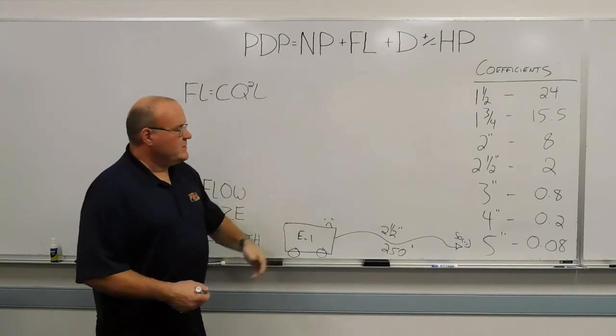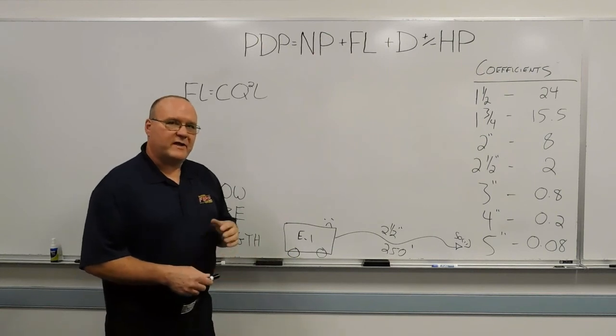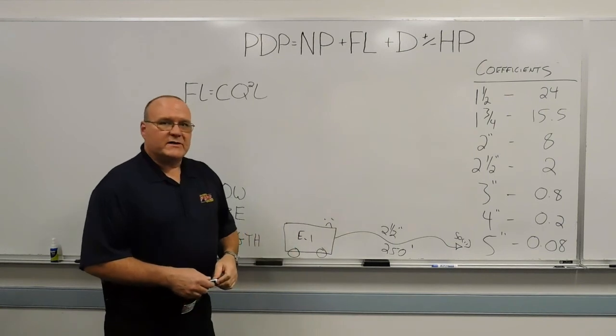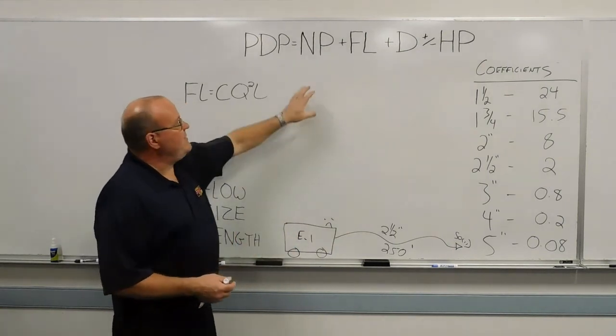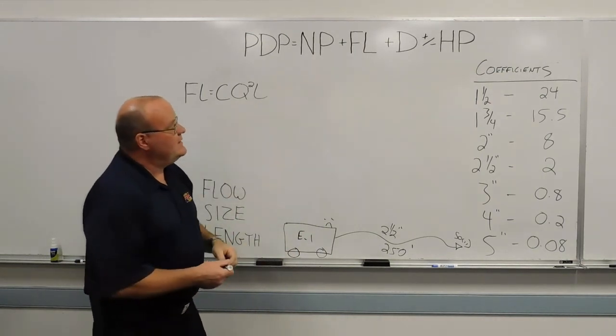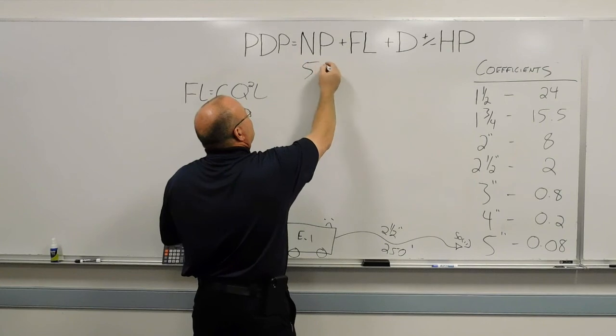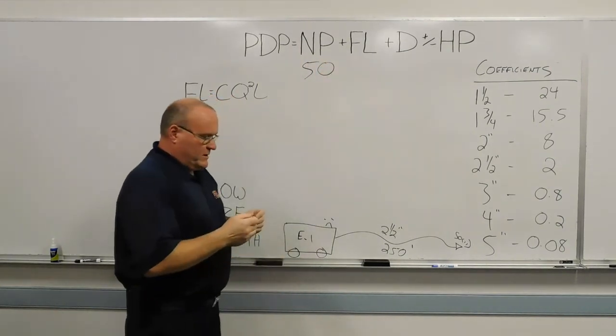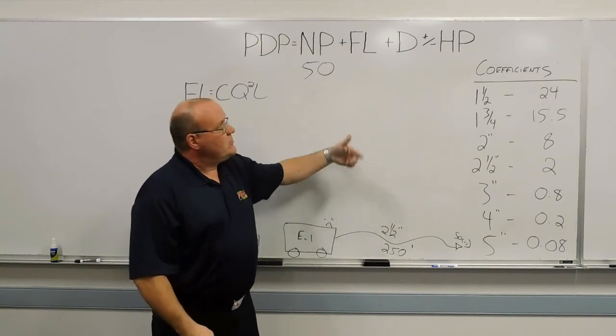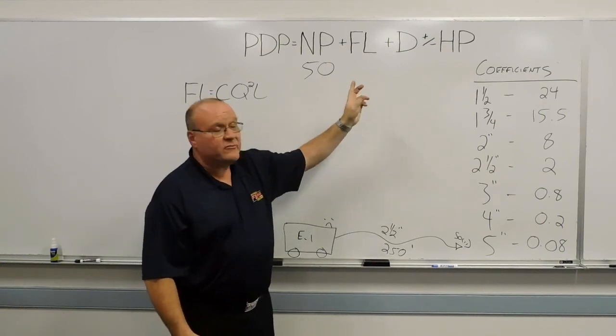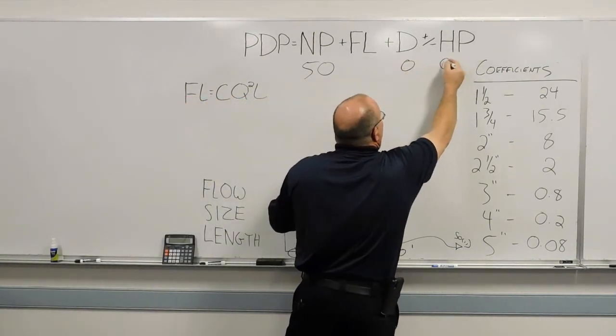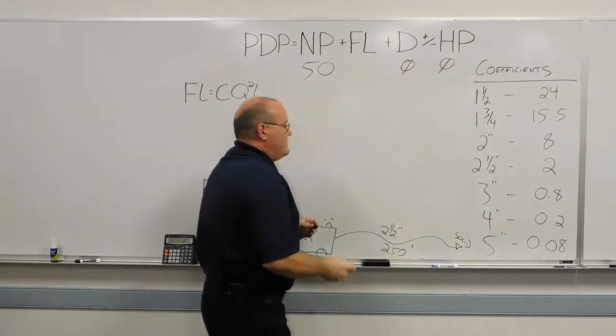So the example that we're going to use here is a two-and-a-half-inch attack line, 250 feet long, with a solid-stream nozzle. So, solid-stream hand line, our nozzle pressure is a given. That's going to be 50 pounds. We can go ahead and plug that in there. And as good pump operators, we're going to account for all four elements. We don't have any devices or any head pressure or elevation changes to worry about in this example. So we'll go ahead and account for those. Zero and zero. And that leaves us with the friction loss.